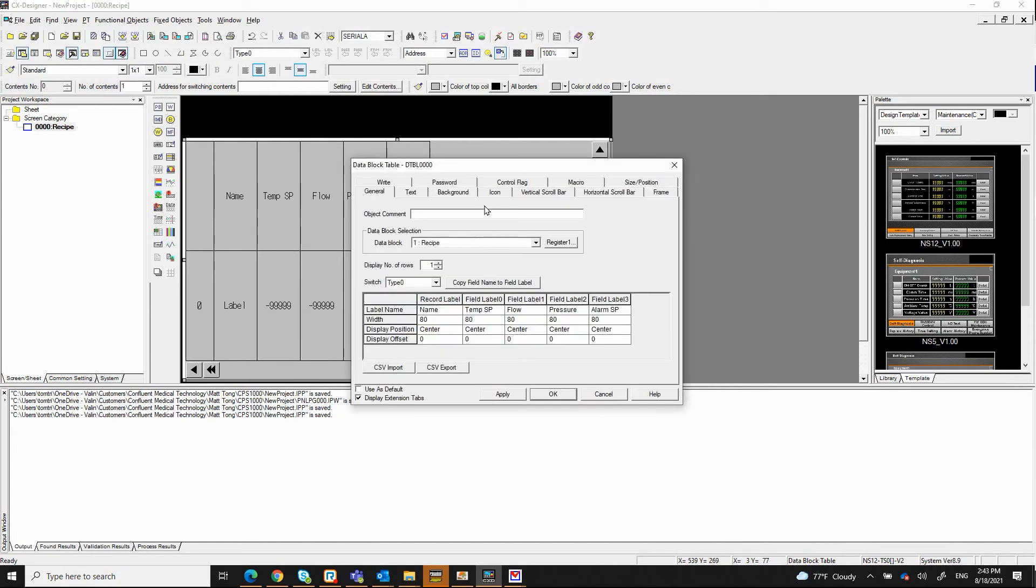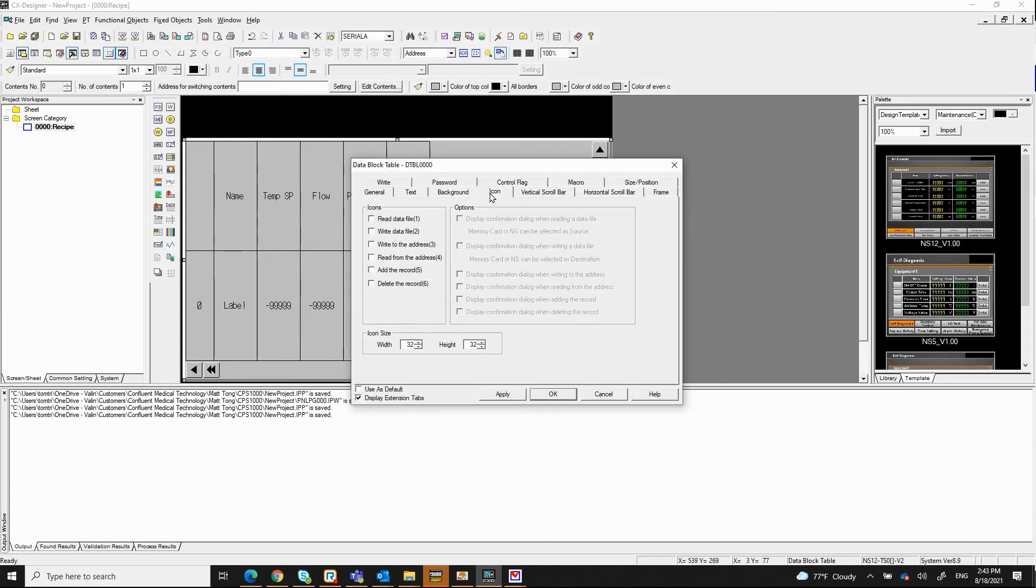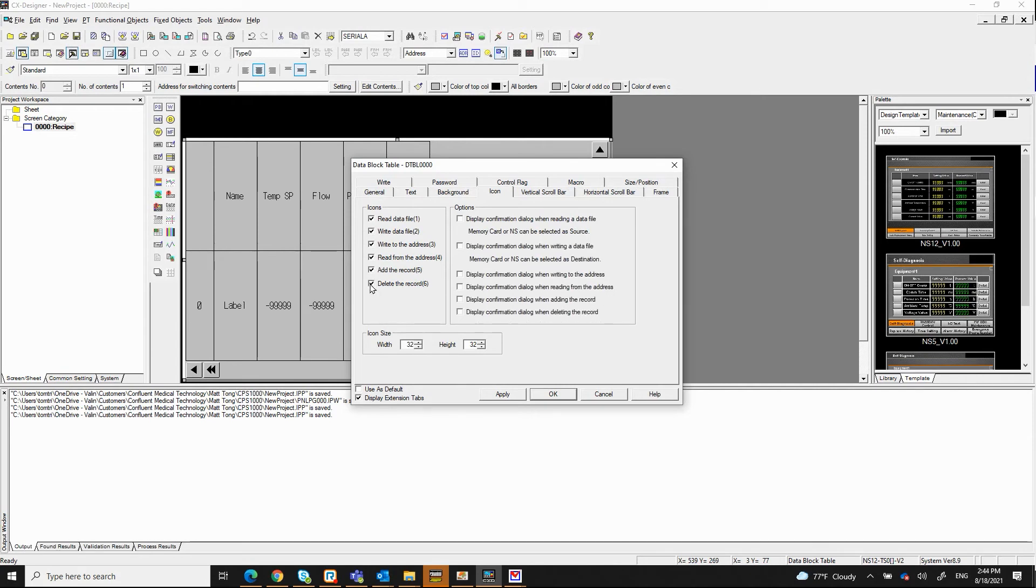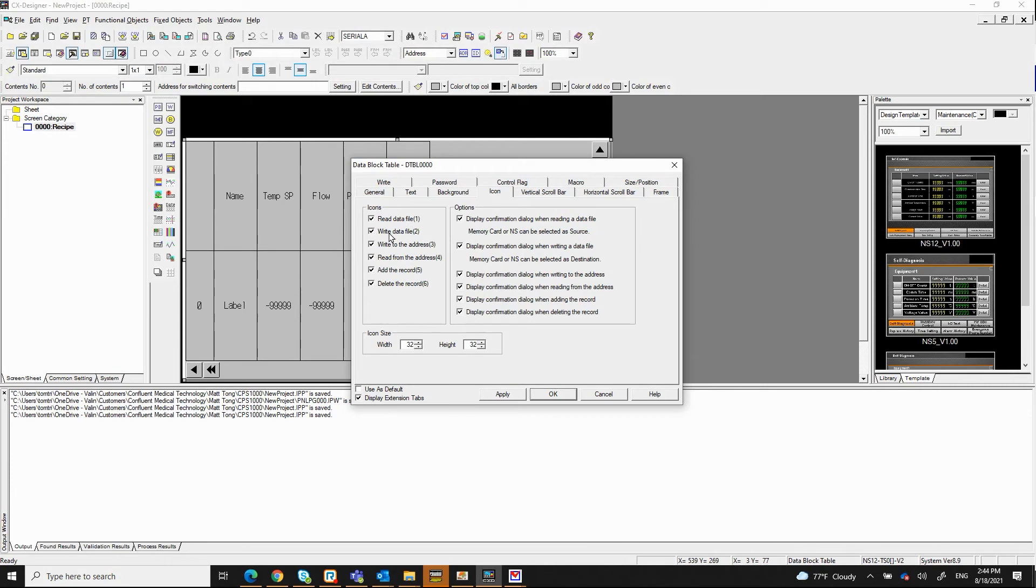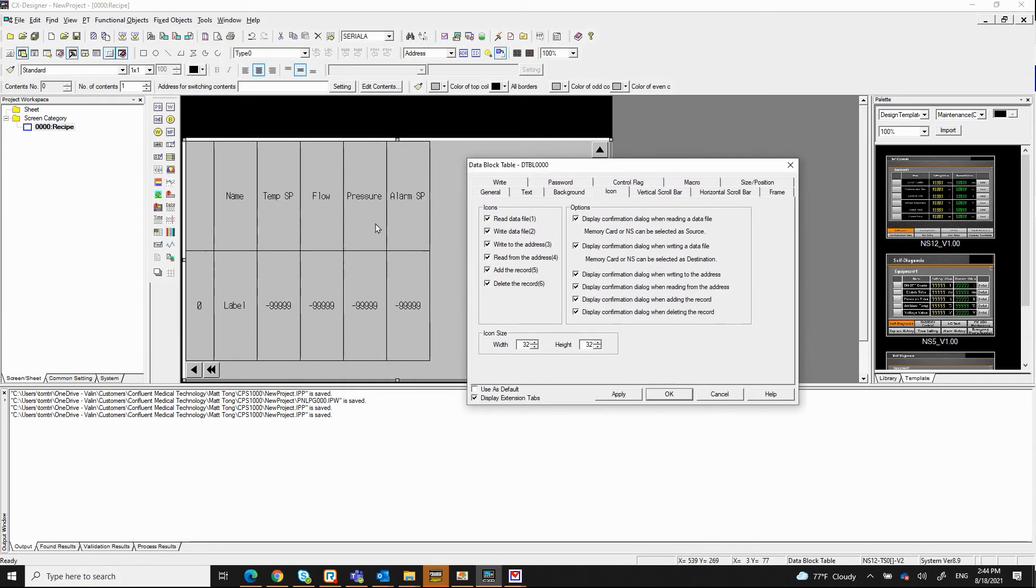What I also want to do next is click on the icon and select all of these icons. All right, and also all the options. What these icons will do for you are for reading the file, the recipe file, or write the recipe file, or write to the address of the PLC that we defined earlier from data memory zero to data memory four for these temperature set point, flow, pressure, and the alarm set point.